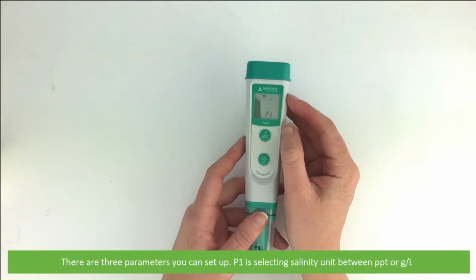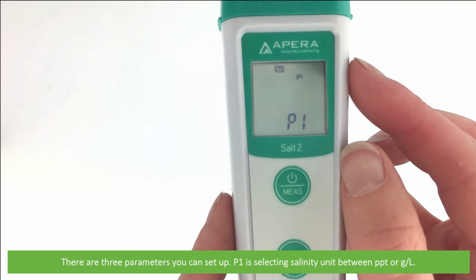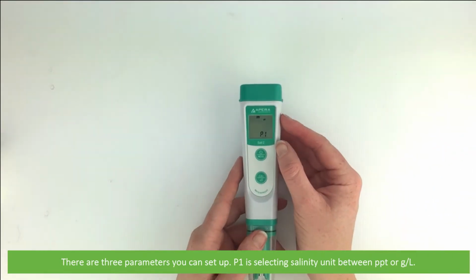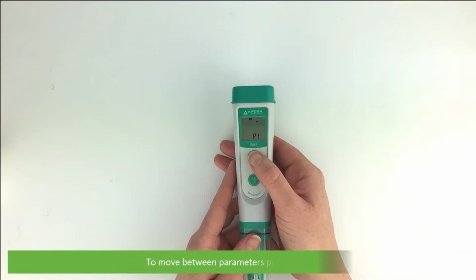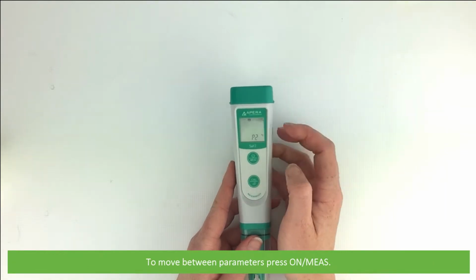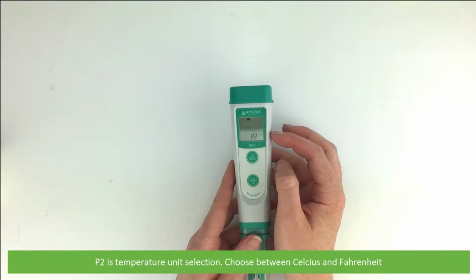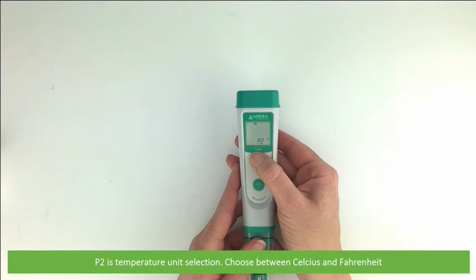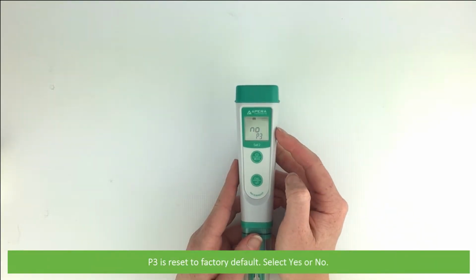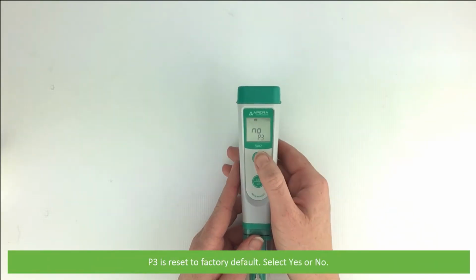There are 3 parameters that you can set up. P1 is selecting the salinity unit between parts per thousand or grams per litre. To move to the next parameter, short press on/measure. P2 is temperature selection, choose between Celsius and Fahrenheit. And P3 is reset to factory default. Select yes or no.